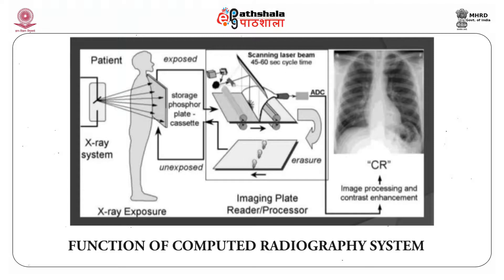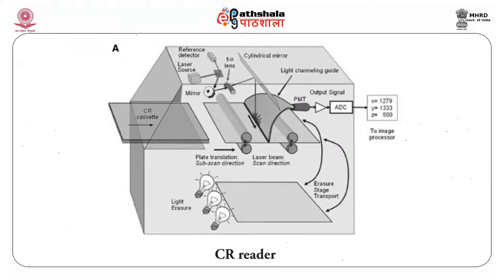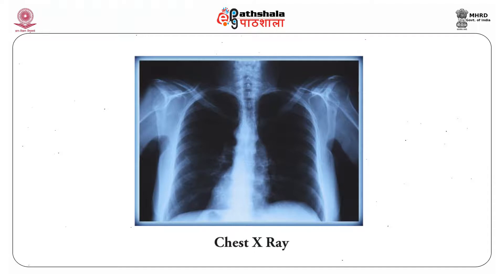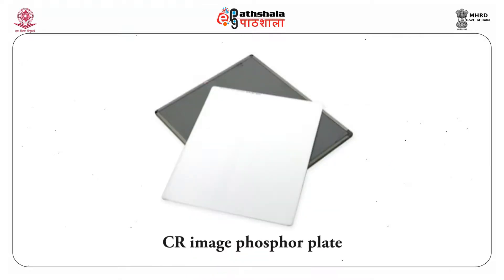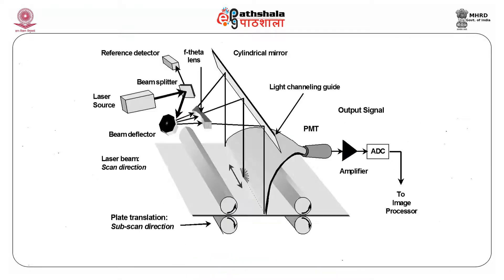This illustrates the function of a computed radiography system in a hospital scenario. You can see an x-ray tube, a patient, and the cassette. The CR reader converts the latent invisible image into a visible image — seen here as a chest x-ray. The main components of a computed radiography system are the image phosphor plate, the laser light used to stimulate the invisible image, and a photomultiplier tube to produce the digital image.